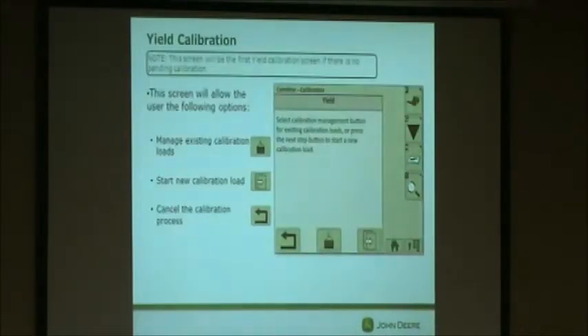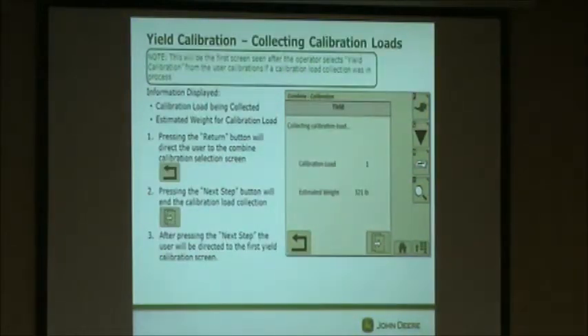If for instance, let's say that you've already got you're full of calibrations from the year before, we need to push this button right down here in the center, and then it'll bring up all your previous calibrations, and you need to go in and delete however many, so we got room to do a calibration. Once we get here, we're going to go to the next step again.